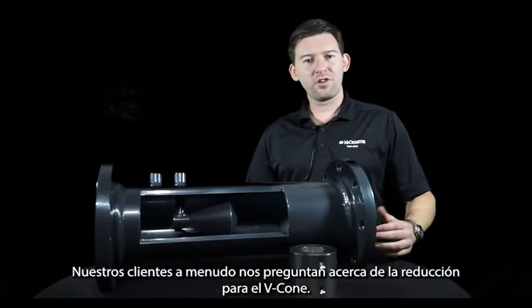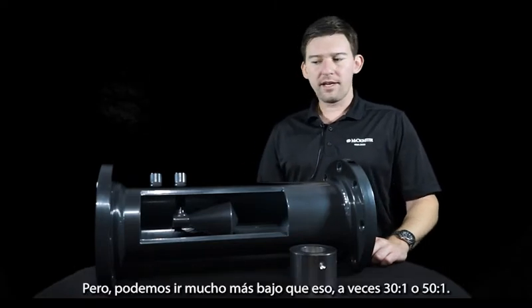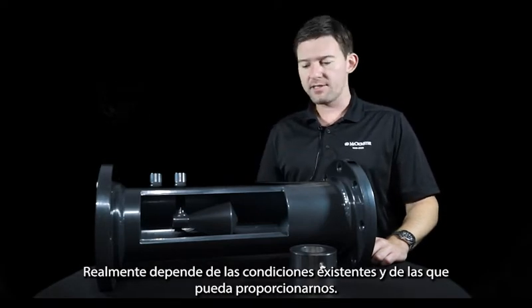Our customers often ask us about flow turndowns for the V-Cone. Standard, we size meters for a 10 to 1 turndown. We can go much lower than that — sometimes 30 to 1 or 50 to 1. It really depends on the conditions that you have and are able to provide us.